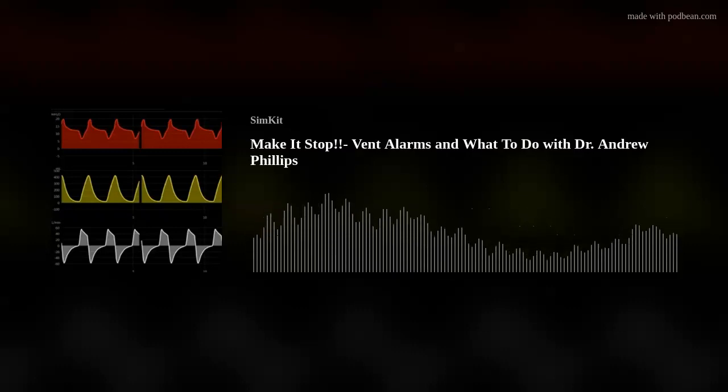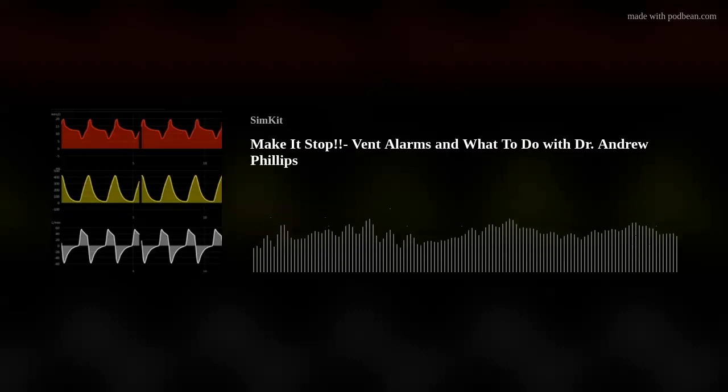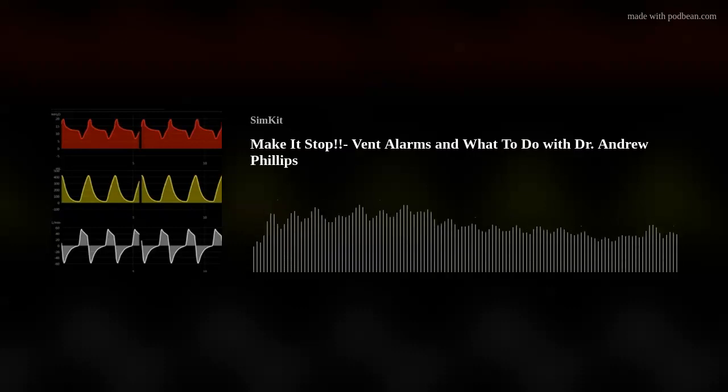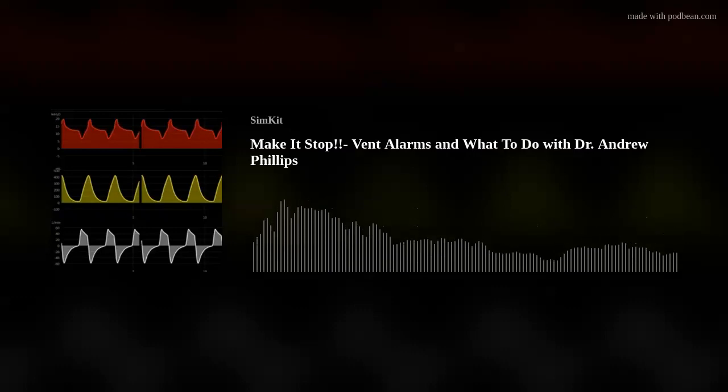Certainly, very much so. And not just the kink, I would add a very common one. Yes, kinking at the bite block, but before you put the bite block on, them biting down on the tube, they're starting to wake up, can cause it. Really, one way to think about the high peak pressure and normal plateau is tubing, some sort of tubing. It's bronchospasm at the lung level. It is biting at the mouth level. It's someone stepping on the tube or the wheels rolling.